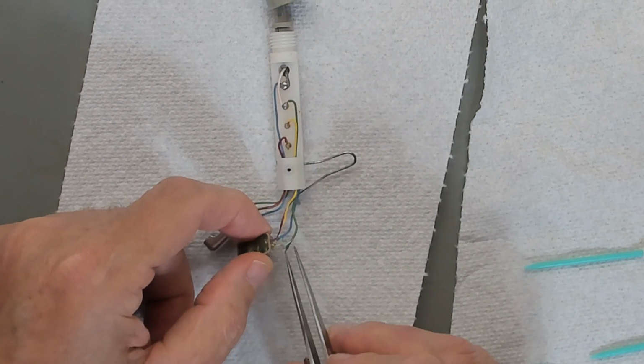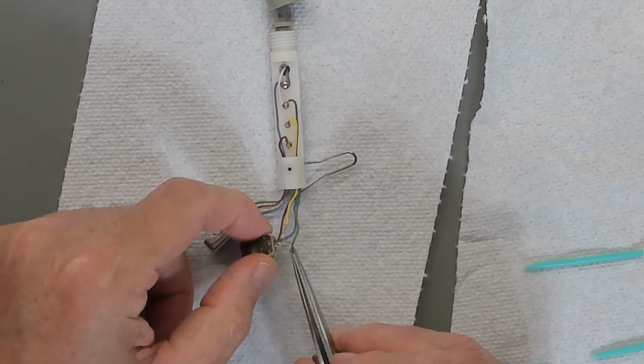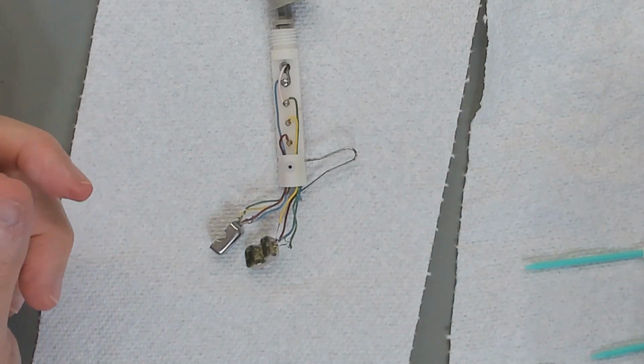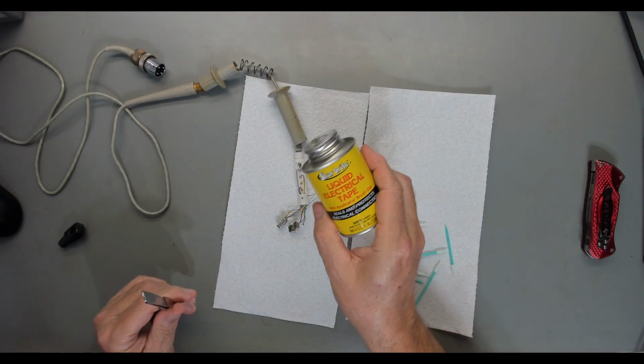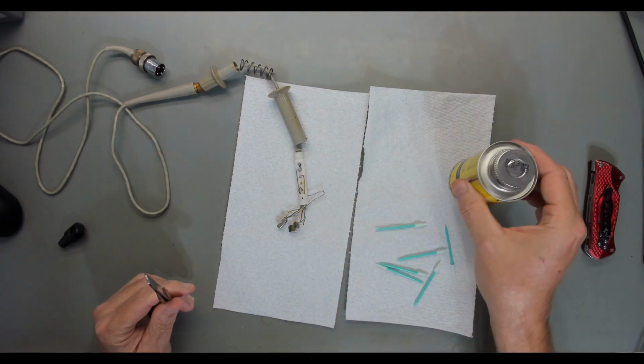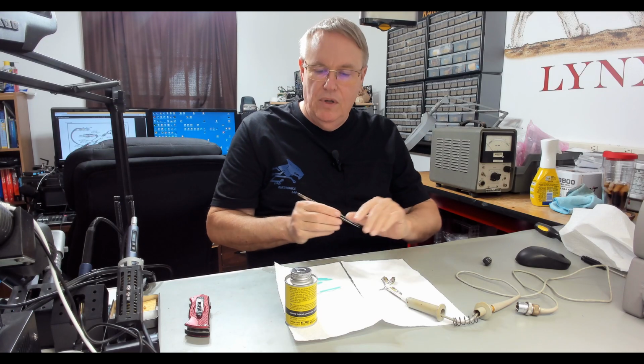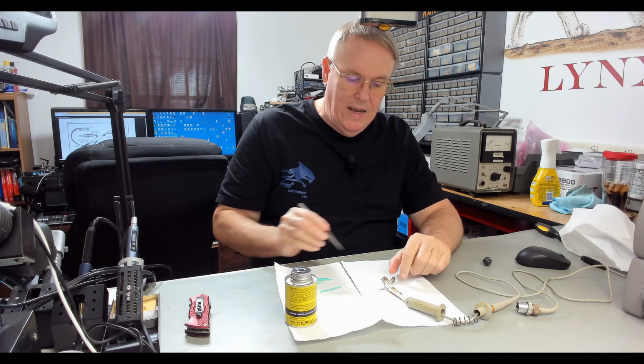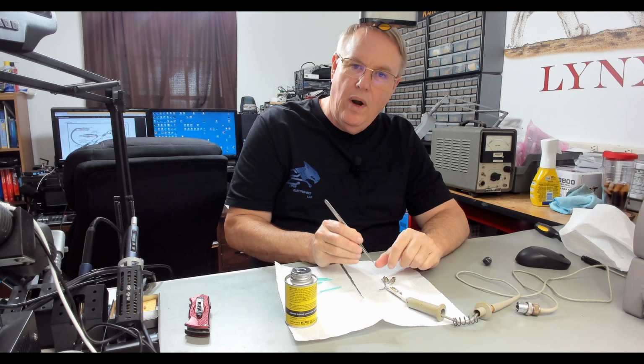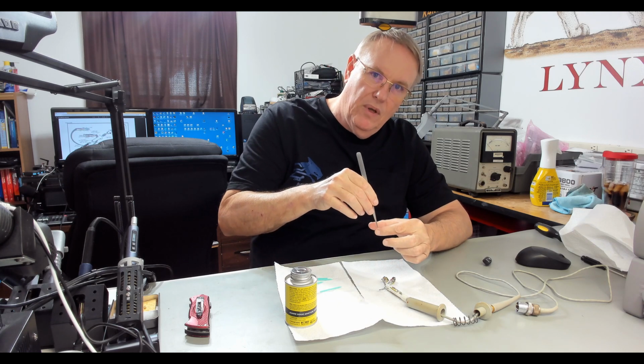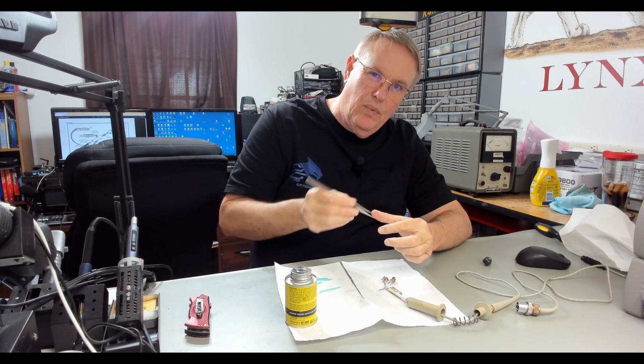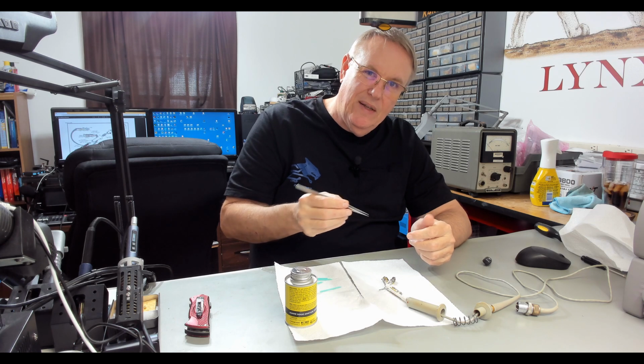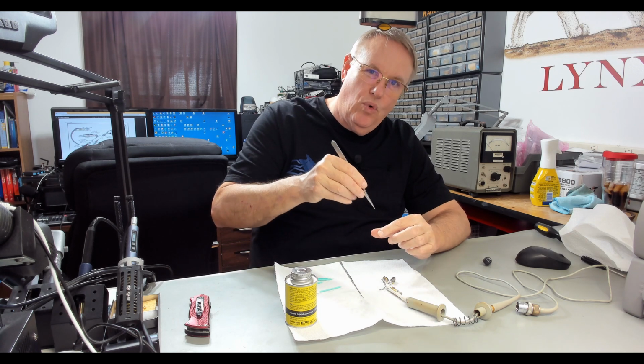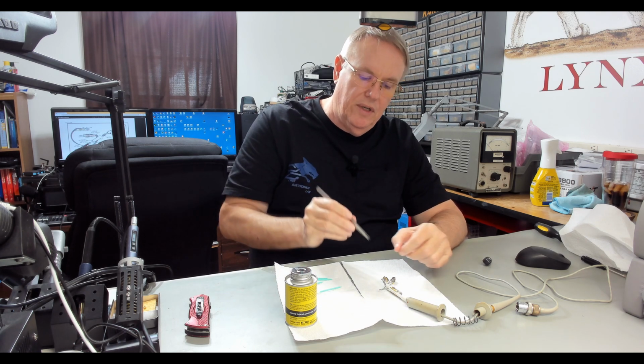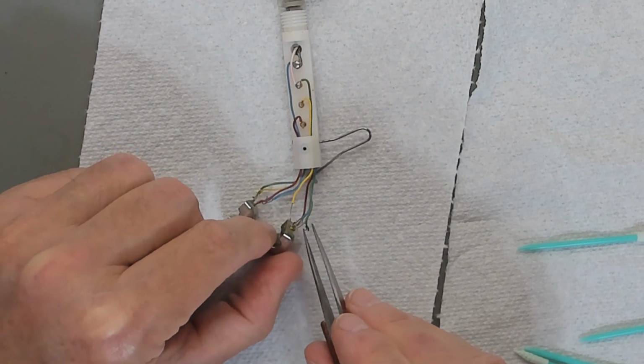And so I'm going to try to clean this insulation off here, and I'm going to do a little microsurgery. What I'm going to do is I've got some of this liquid electric tape that I've used before, and I'm going to try to spread the wires and coat the very bottom of the middle with a little bit of it. Bring them close together but not touching, and let that set up, and then coat the outside, and then work my way up, putting coatings on, and actually try to replace this insulation.